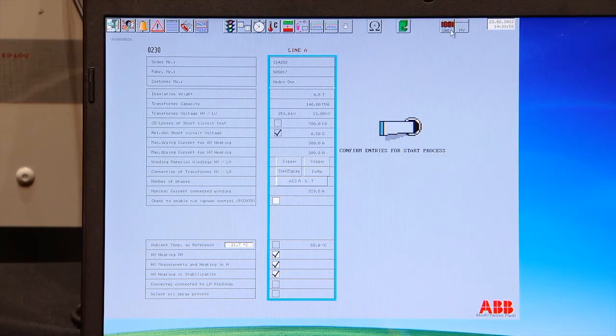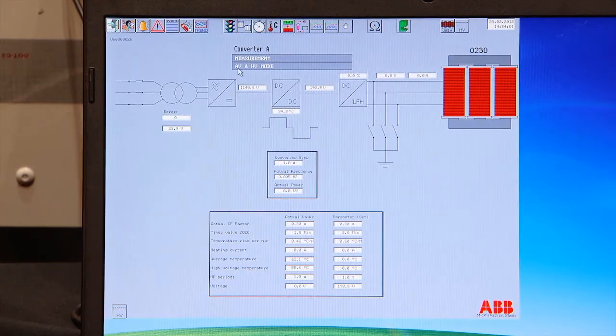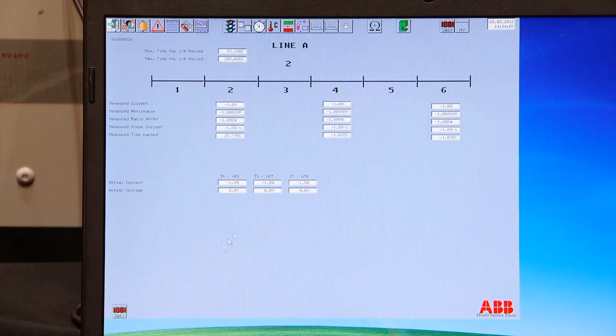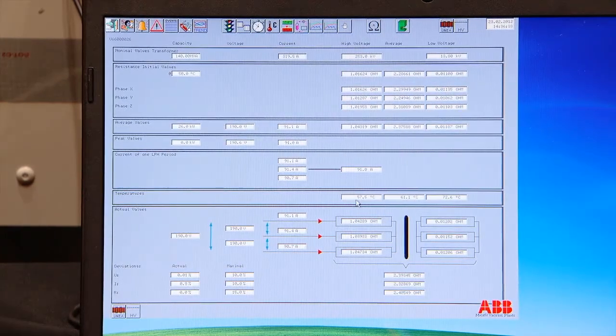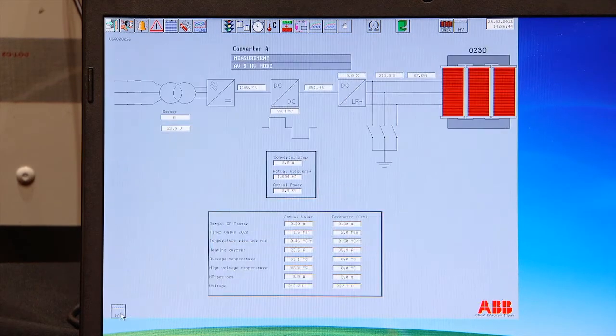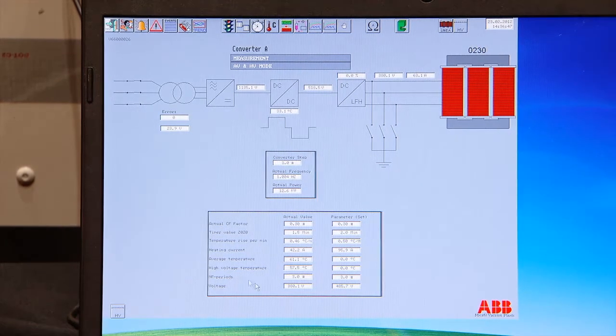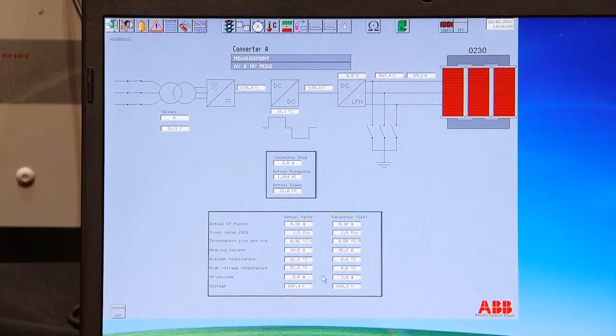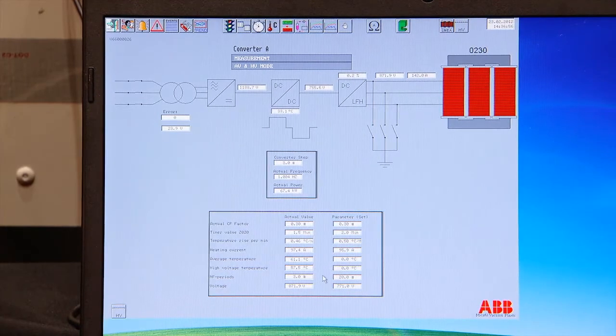What he has done is that he's going into AV and HV mode, average and high voltage mode, in measuring. And we are now in second phase, so he's taking the readings, which tells us that he's taking the temperature readings. Temperature reading at the high voltage, 57.5 degrees. I think we are in demagnetization at the moment. What was the low there? 72. He has not calculated that yet. Oh, okay. There was a value. It's an old value. It's updated after demagnetization.